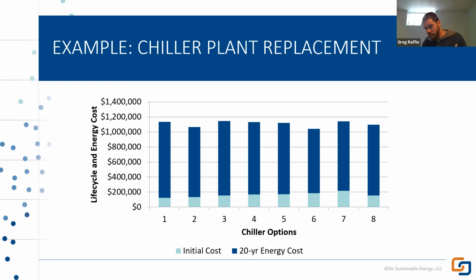We worked with building representatives and the design team to select the chiller more intelligently. We got data that chiller manufacturers don't usually give out, but told them they couldn't bid unless they provided it—so it magically showed up. We ended up with 8 chiller options for this facility.